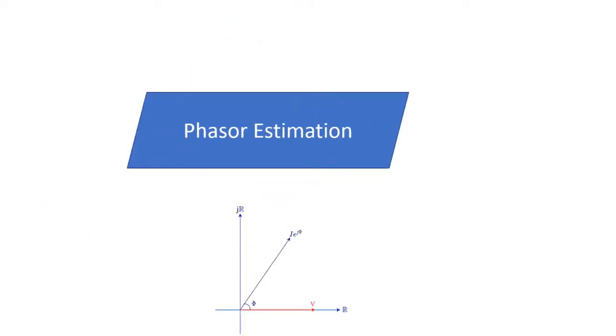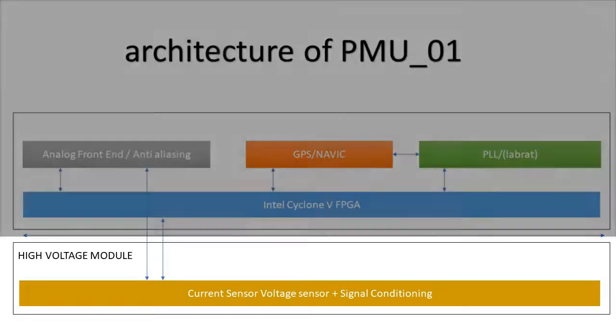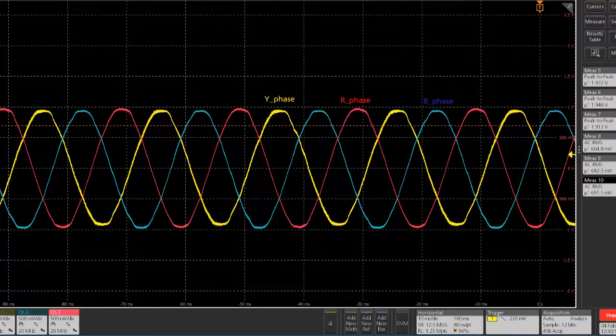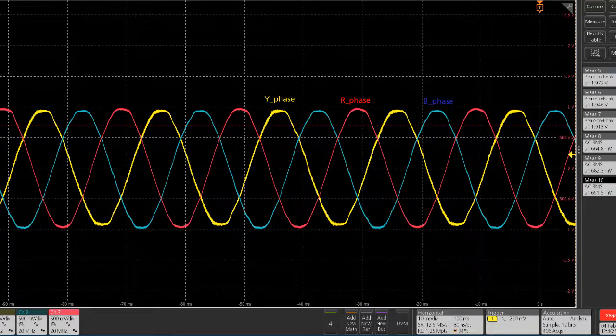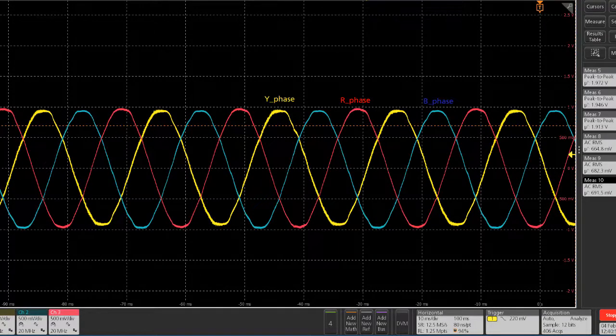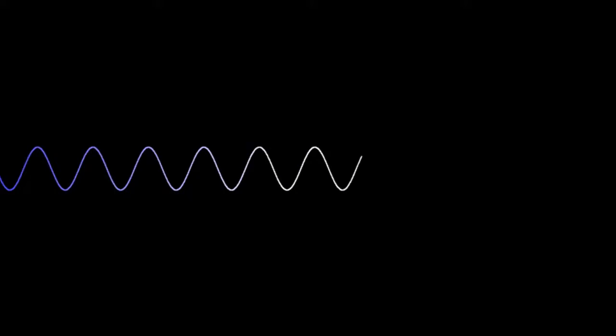It reports to PDC at 100 frames per second following IEEE C37 standard. The high voltage module steps down the voltage level output from substation CT and PT to a suitable level good for digital signal processing. It uses Hall effect-based sensors to provide noise-free transformation, after which analog to digital converters digitize the analog waveform.